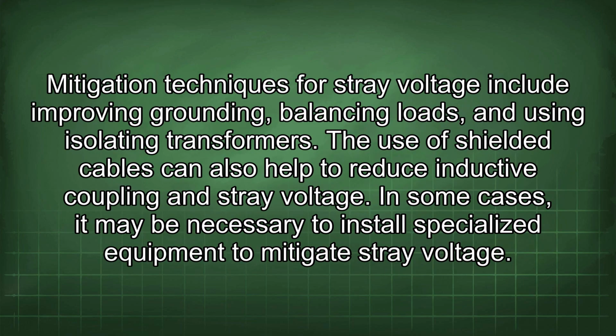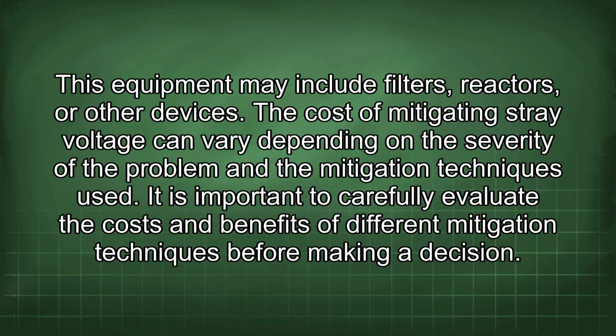Mitigation techniques for stray voltage include improving grounding, balancing loads, and using isolating transformers. The use of shielded cables can also help to reduce inductive coupling and stray voltage. In some cases, it may be necessary to install specialized equipment to mitigate stray voltage. This equipment may include filters, reactors, or other devices. The cost of mitigating stray voltage can vary depending on the severity of the problem and the mitigation techniques used. It is important to carefully evaluate the costs and benefits of different mitigation techniques before making a decision.